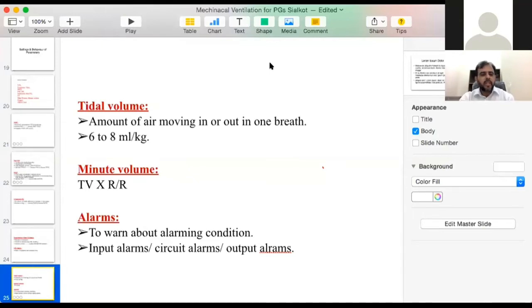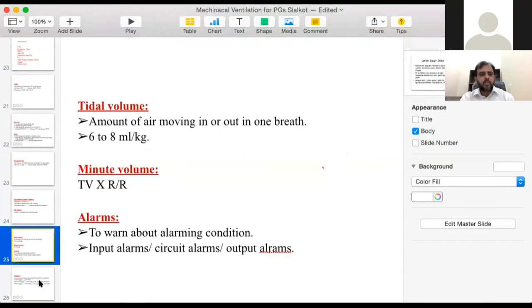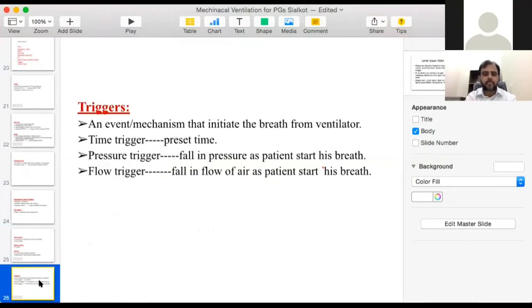So alarms are set to set the limits that the ventilator should not go beyond the permissible values. What are the triggers? Actually, in the new ventilators, this is how the ventilator synchronizes with the patient's breathing. The old ventilators had no mechanism of synchronization. You put the patient on a ventilator and you set a rate, you set all values, and the machine will operate. It will not see what the patient is doing, whether the patient is inhaling or exhaling. The machine will not come to know.